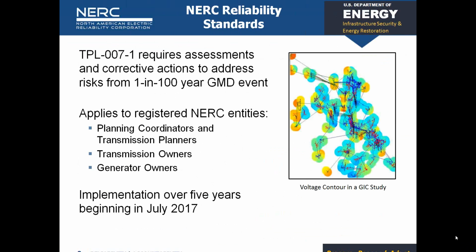The standard requires entities to use the state-of-the-art modeling tools that are available to then use that storm and simulate the GIC flows that they would see on their system, and model how the system would respond to that. And then if the system were to not meet the performance requirements, if it were to lead to a voltage collapse, for example, then that entity would be required to develop a corrective action plan that would allow them to prevent that situation from happening.